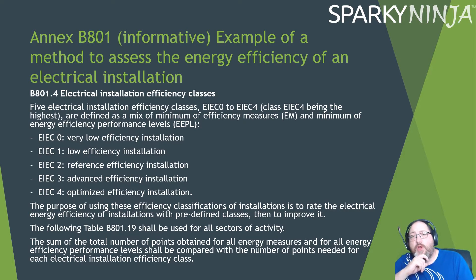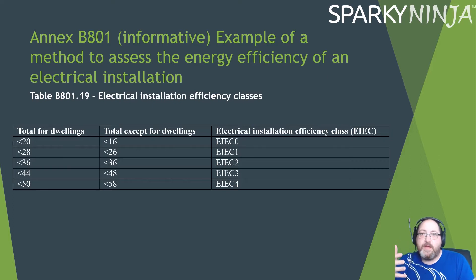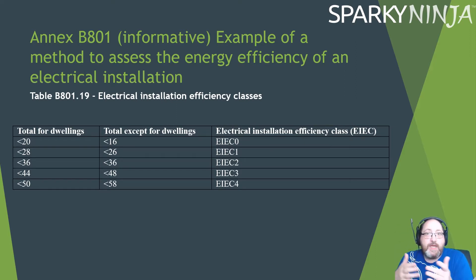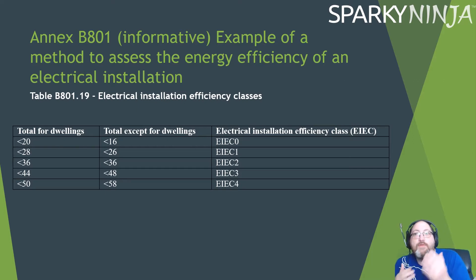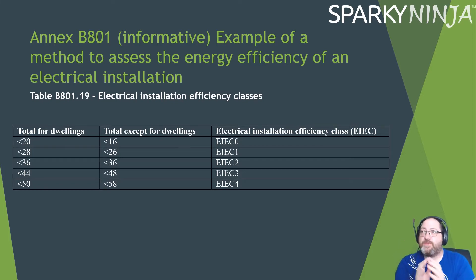EIEC zero is 'very low' and EIEC four is 'optimized.' The purpose is to rate the electrical energy efficiency of installations with predefined classes and then work to improve it. For dwellings, a total score of less than 20 — from lots of zeros and ones — gives EIEC zero; a score over 50 from lots of fours and threes gives EIEC four. The scoring differs between dwellings and other sectors, and this final table is your overall score sheet.